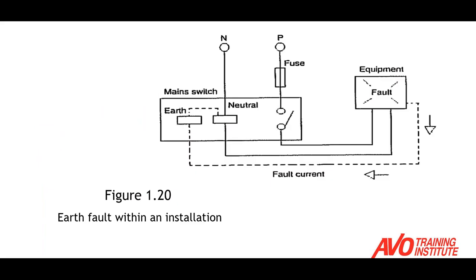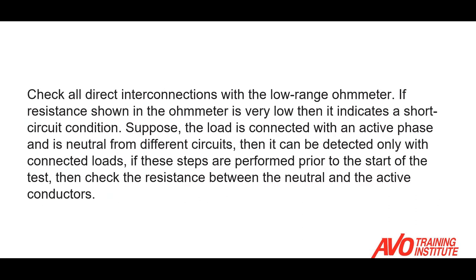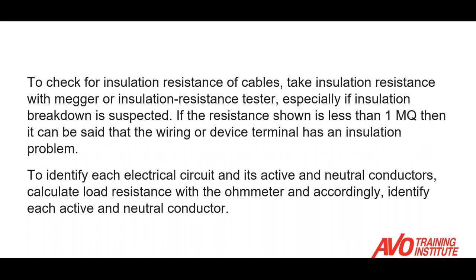A continuity test is useful to detect a short circuit condition. It can help us pick up incorrect termination of wires, insulation breakdown, or any incorrect connection at a field junction box. Before this test, we need to disconnect the neutral link from the circuit and close all contactors and switches, then check all direct interconnections with a low-range ohmmeter. If the resistance reading is very low, we have a short circuit condition. After that, check the insulation resistance of the cable with an insulation resistance test. If the resistance read is less than one mega ohm, then the wiring or device has an insulation problem — though that one mega ohm value may change based on the requirements of your company or installation.